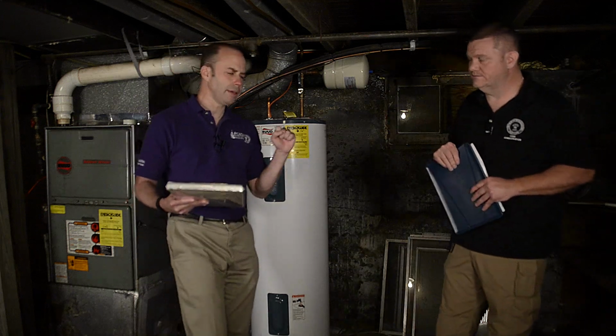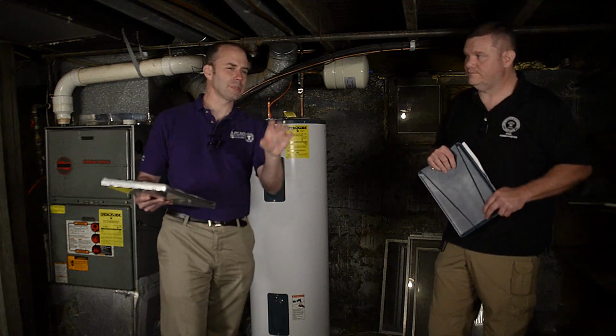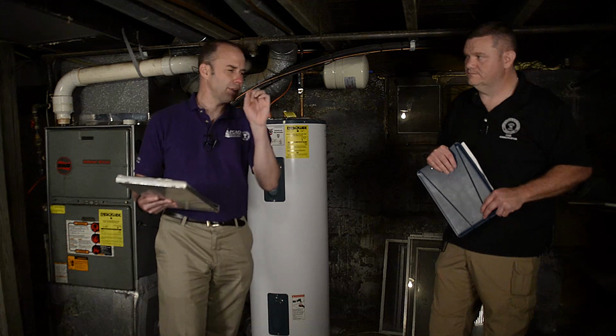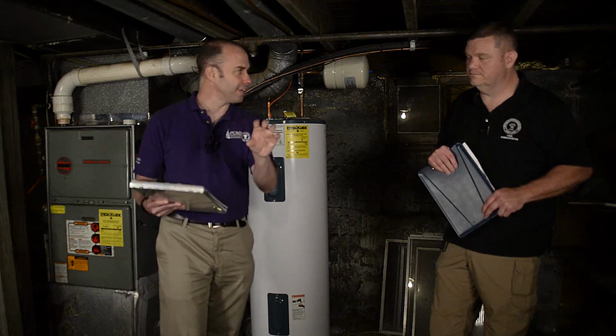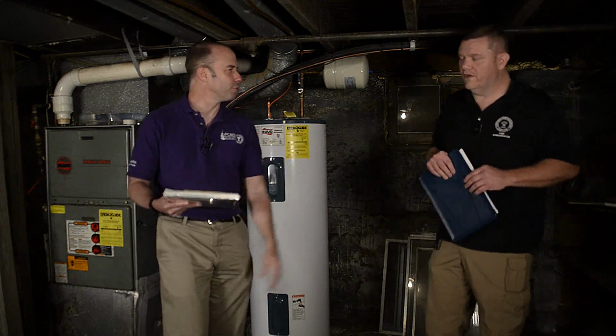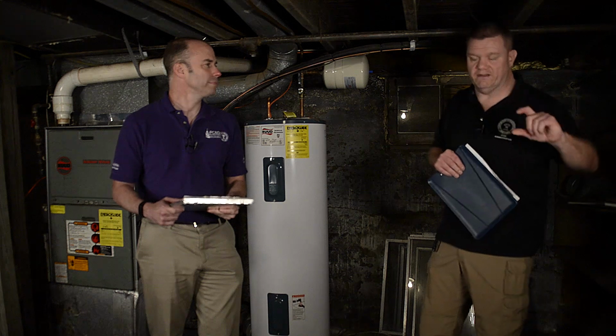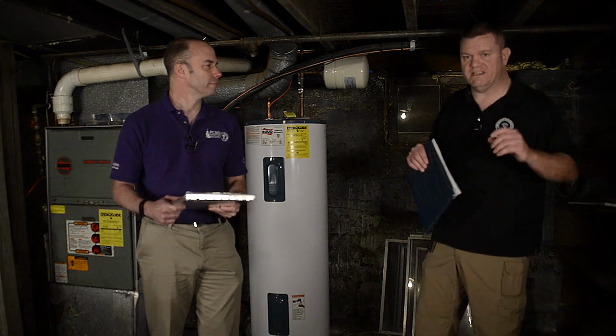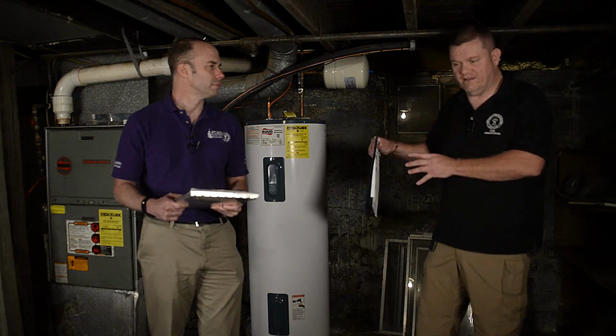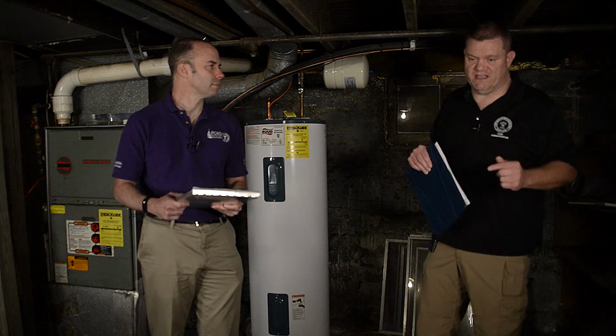All right, thank you. And let's say that I do have a washer dryer hookup and I am right beside a laundry sink, and I need to plug my washer into that outlet. What are the requirements for that again? I can't remember if you covered that. Yes, with the plug, we do require it to be grounded. It's a metal appliance, so it does have to be a grounded plug. Now, with the laundry sink, in that neighborhood of it, we do then require it to be GFCI.